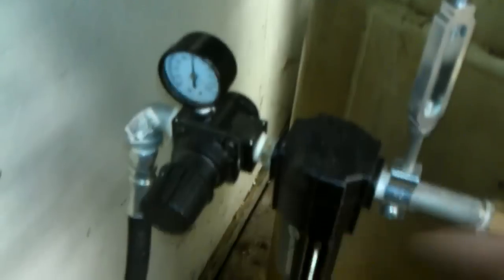valve up here or down there, just to keep air pressure from moving back up into here. I don't care if the moisture goes down there, because the tank drain will bleed out, but I can't have it the other way around. I can't have any moisture from the tank drain going back up into here, filling this up, and then going through the whole circuit.